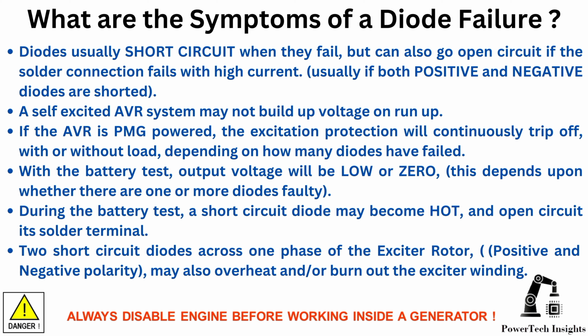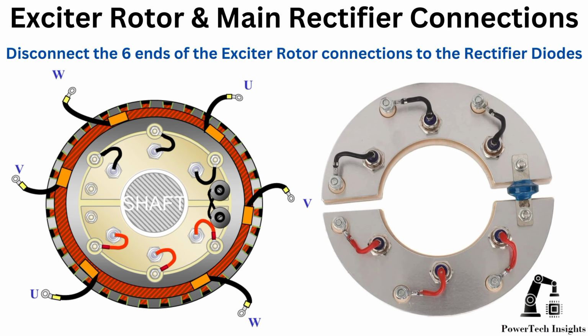A self-excited AVR system may not build up voltage on run-up. If the AVR is PMG powered, the excitation protection will continuously trip off, with or without load, depending on how many diodes have failed. With the battery test, output voltage will be low or zero. This depends upon whether there are one or more diodes faulty. During the battery test, a short-circuit diode may become hot and open-circuit its solder terminal. Two short-circuit diodes across one phase of the exciter rotor, positive and negative polarity, may also overheat or burn out the exciter winding.